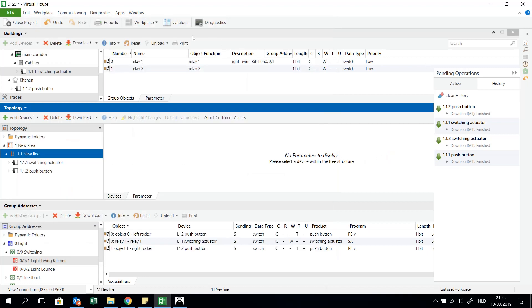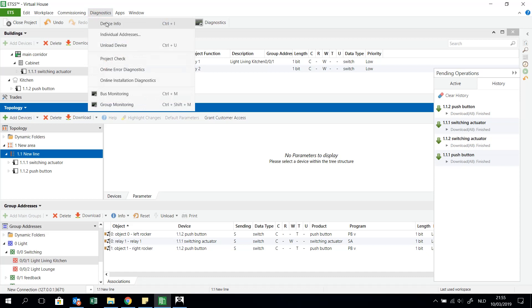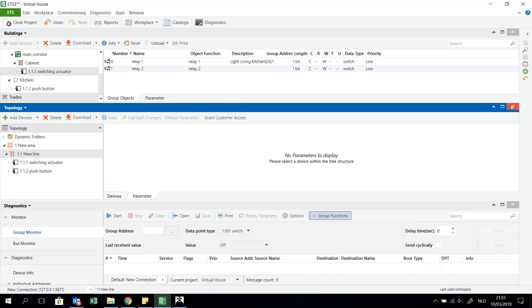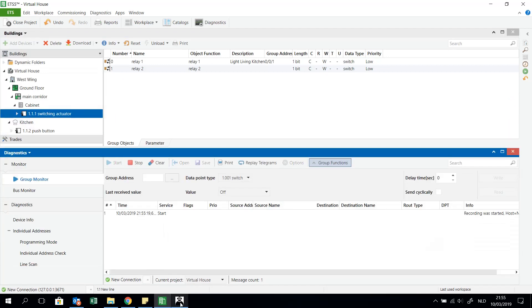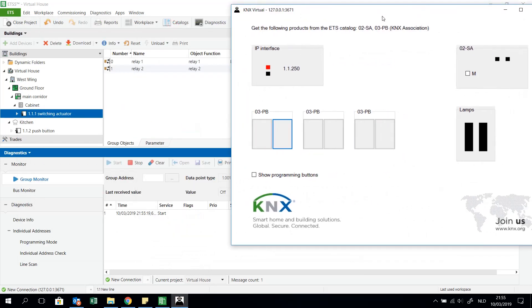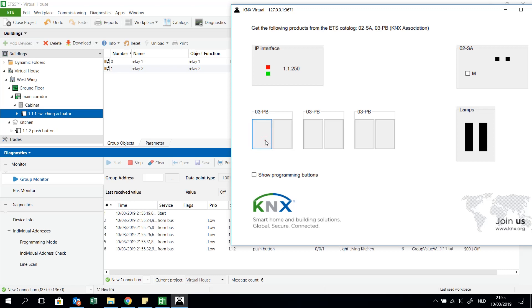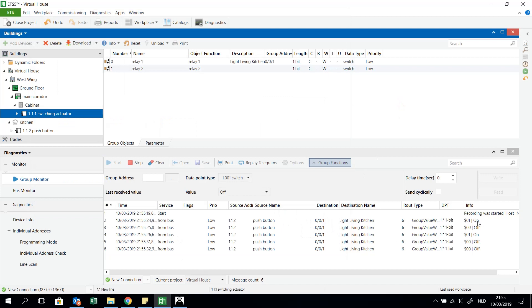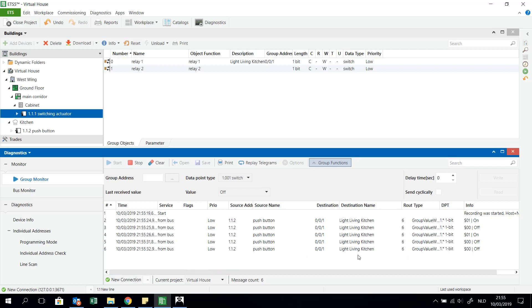The most interesting thing is that I can now also do a lot of things in the diagnostics. For example, I will start a group monitor. When I am sending telegrams to turn on the light, turn it off, turn it on, and wait five seconds, I can see all activity. I can see the source address, the destination address, the route counter, and the DPT — all this information can be very interesting. I will then stop the group monitor.